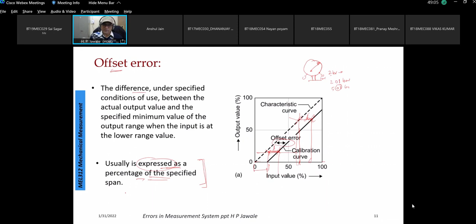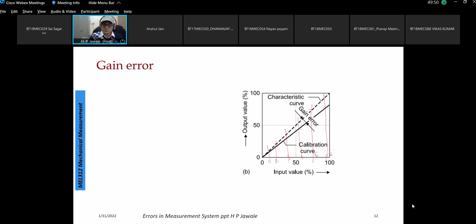Okay. Then we come to the gain error. It is a multiplicative error. Just now we have seen measurement of the temperature by thermocouple junction. Say for a given input, these are the inputs I have divided: input 1, 2, 3, 4, 5. These are the different temperatures, let us say. In actual practice, it has to show something related to the calibration curve, the standard curve given for the instrument, but it is showing something higher. Here it is small, it is increased. For the third, it is still increased further. It is increasing with some rate. So this is the gain error. The slope of the characteristic curve differs from that of the calibration curve.